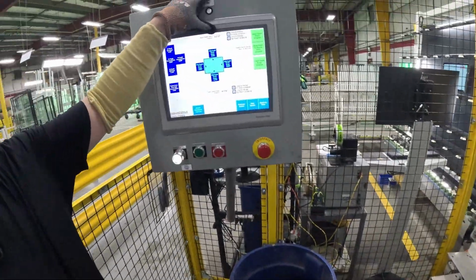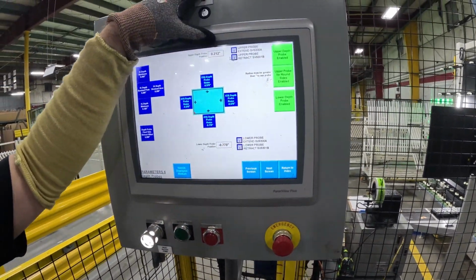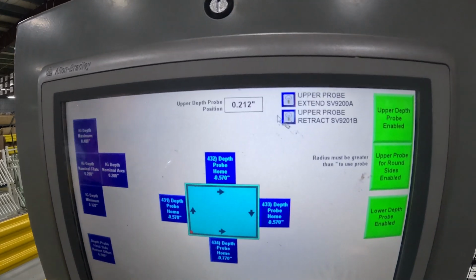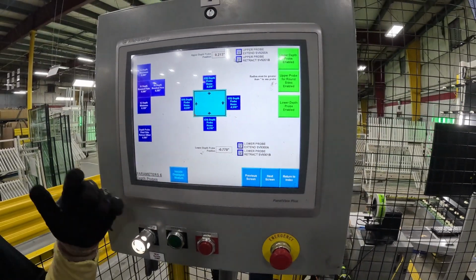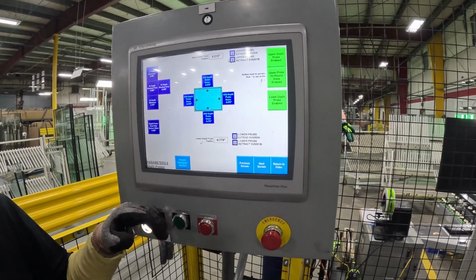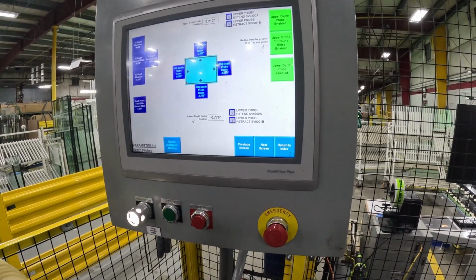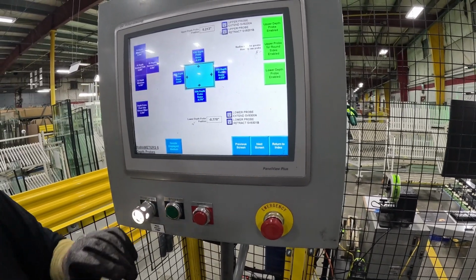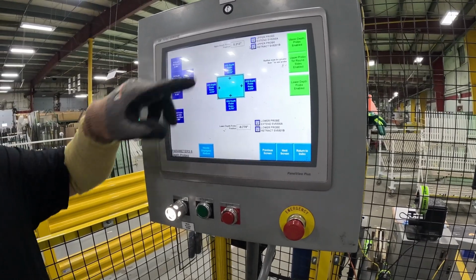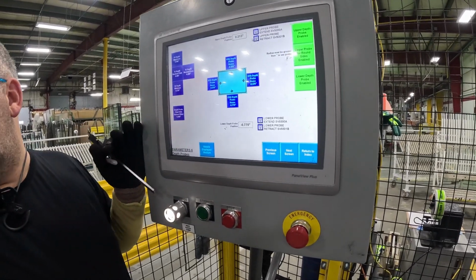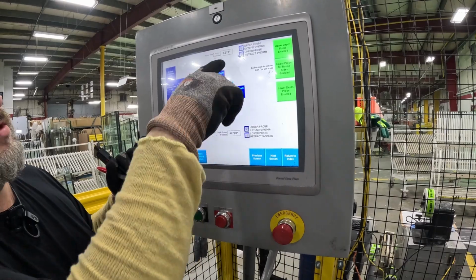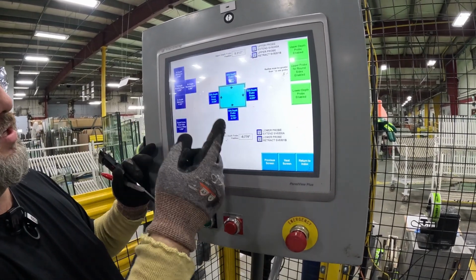Now you can look on your screen and we have a measurement of 0.212. That's reading 0.220. If you're within about 25 thousandths, you're close. It's close enough. It'll be fine. It's always going to vary a little bit. So if, let's say we want to get this a little closer to 220. So we're at 213 right now.